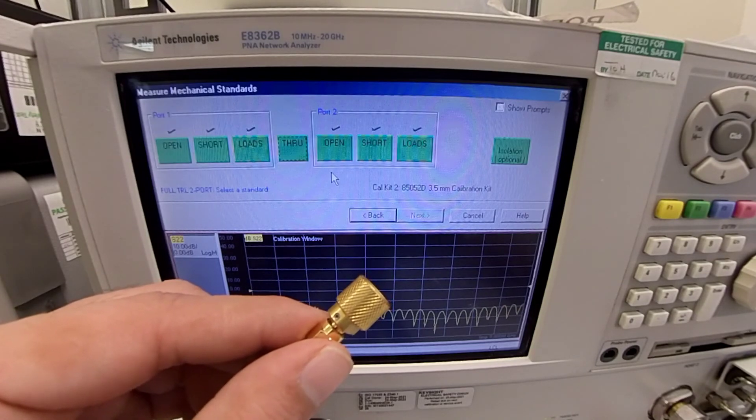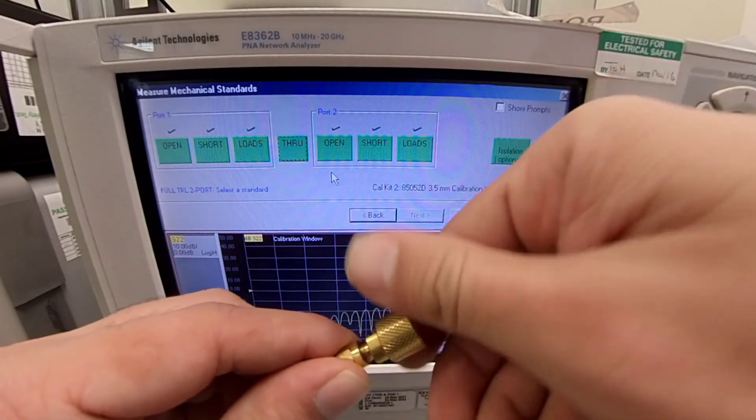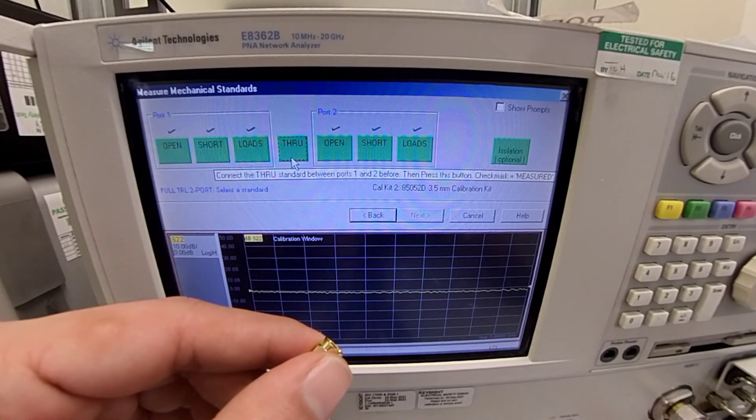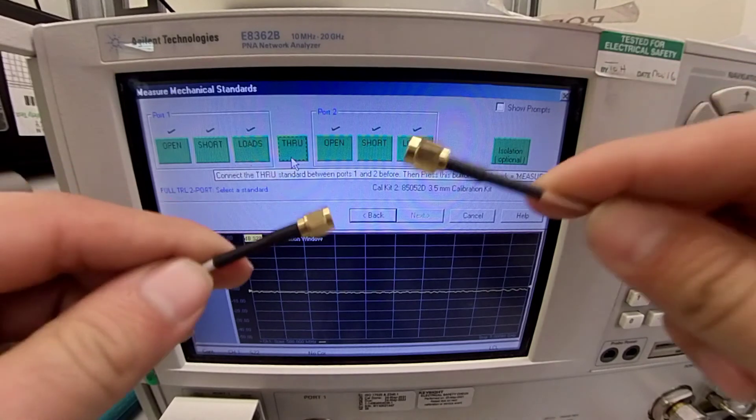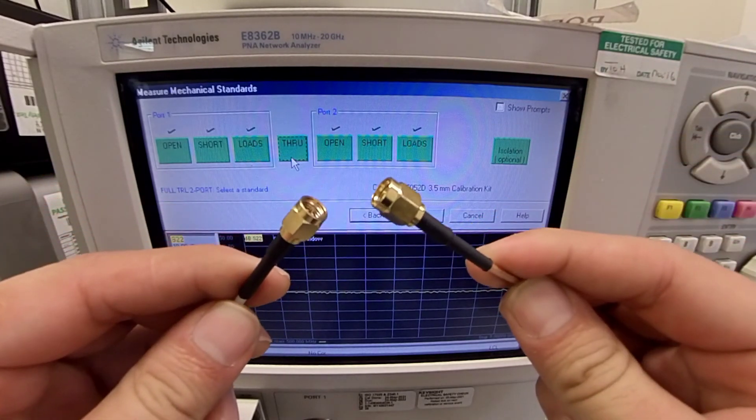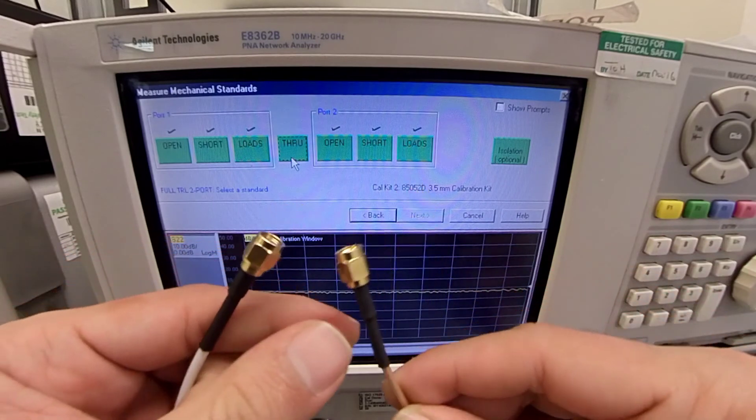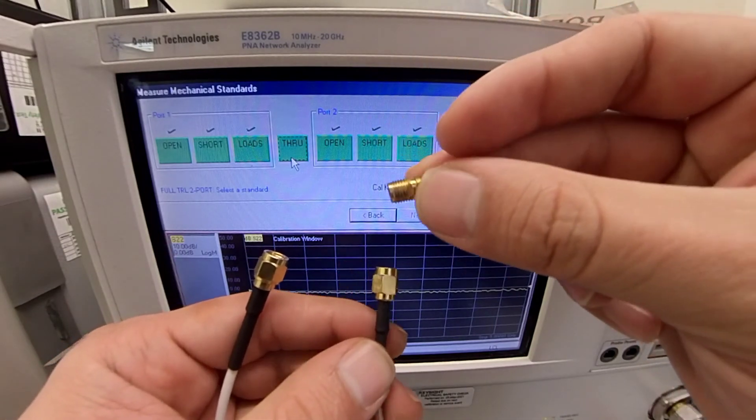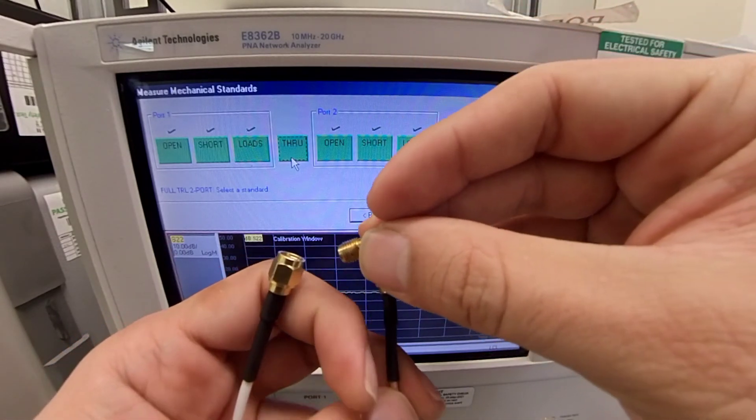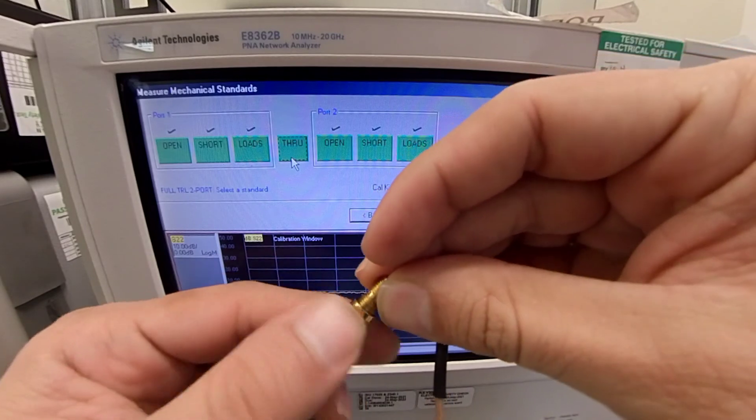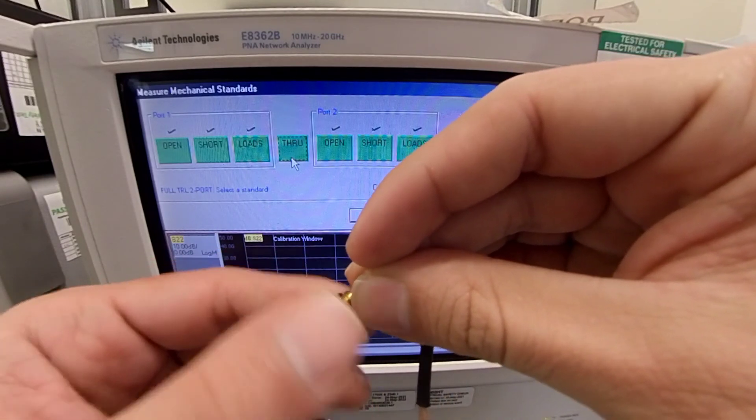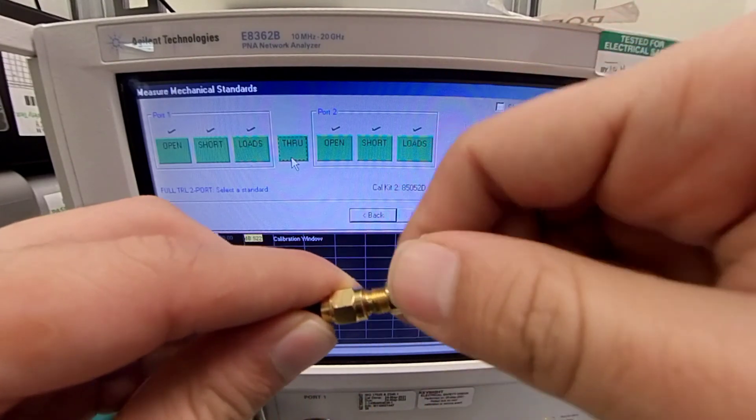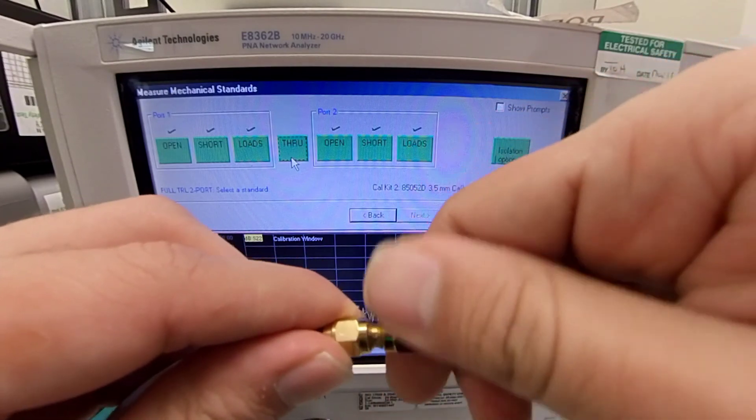And now comes the final step in the calibration process. The through calibration, you can see on the screen, requires both the cables to be connected to one another. As you can see, we cannot connect them directly, but we need a connector or adapter in between. From the calibration kit, I select a specific connector that connects both the male connectors. I perform the calibration in this way. As you can see, I have connected both of the cables, which is normally called through calibration process.